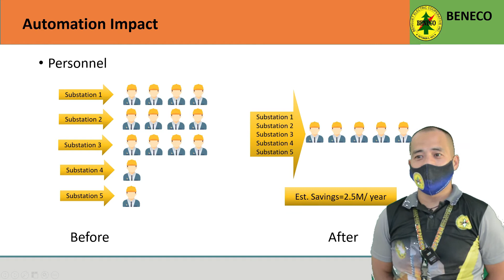Number 3, personnel. In the past, 14 substation tenders on a shifting schedule for the 5 substations to manually record data and operate protective devices. Today, there are only 5 engineers monitoring all the 5 substations. In shifting schedule, only security guards are at the substations to secure and watch over the equipment, with which Beneco saved 2.5 million per year for this. But nevertheless, the displaced tenders were not dismissed, but rather, they were realigned to be linemen and as meter readers.